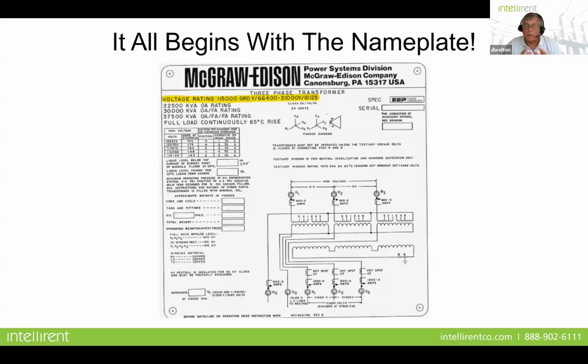Pretty much every setting that you're going to put into the relay, including the differential, comes from information on the nameplate itself. And sometimes they can be very difficult to read because not all nameplates look the same or are arranged the same. So if you're a person that's responsible for setting or testing a protective relay, you have to understand what this information is telling you. If you're a person that actually goes out and does testing, maintenance testing or commissioning on a transformer, you have to understand what this nameplate is telling you.